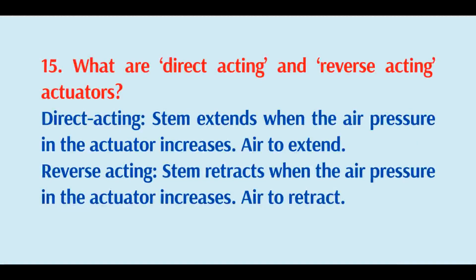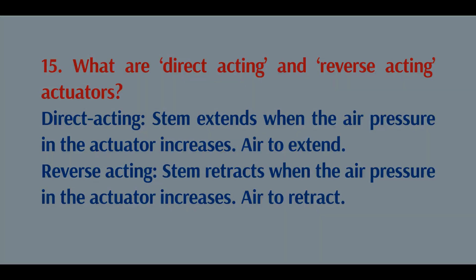What is a direct acting and reverse acting actuator? Direct acting: the stem extends when air pressure in the actuator increases — air to extend. Reverse acting: the stem retracts when air pressure in the actuator increases — air to retract.